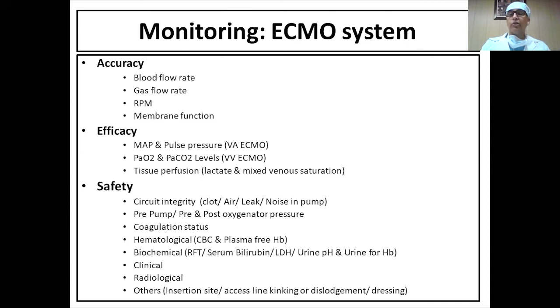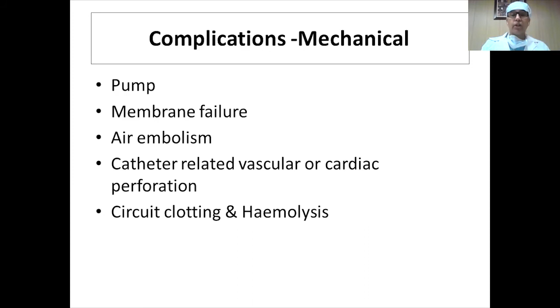But we should be ready for any kind of complication when a patient is on ECMO: a pump failure, malfunction of the pump, or even the membrane can fail, which can stop the gas exchange and the patient can collapse. There is always a risk of air embolism if there is a leak in any system on the negative side. There can be risk of catheter-related vascular or cardiac complications. Any perforation can occur. There can be circuit clotting and even hemolysis if the pump head is not working well.